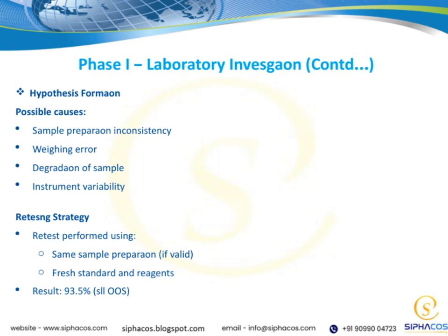We considered several possible causes for the out-of-spec result. These included potential inconsistencies in sample preparation, weighing errors, degradation of the sample over time, and variability in the instrument's performance. This phase is crucial because understanding these potential causes guides us in pinpointing the root of the issue, ensuring that we address the actual problem rather than just the symptoms. This investigation forms the foundation for improving our processes and preventing similar issues in the future.